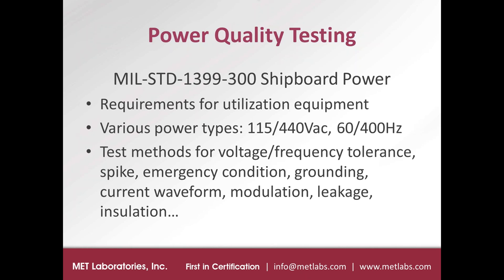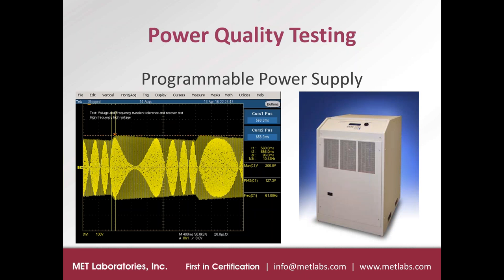And the test methods within MIL Standard 1399-300 cover different parameters such as voltage and frequency tolerance, spike, emergency condition, grounding, current waveform, modulation, leakage, insulation, and more. This slide shows a photograph of a programmable power supply on the right, and on the left is an oscilloscope plot, which would be a typical plot captured for something like a voltage and frequency tolerance test. This is the main type of test equipment. This programmable power supply would be the main test equipment used to perform most of the testing out of those standards. Some of the tests would require other equipment like transient generators and some of the other equipment that's used for MIL Standard 461 low frequency type testing.